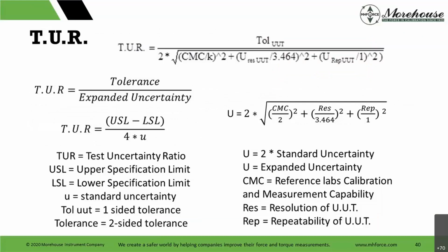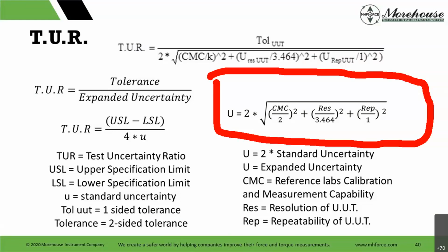The definition I like is ILAC P14 when it talks about short-term contributors. I'm putting this up as really a minimum, right? For this denominator, if we go to ANSI Z540, it's going to say you're going to include the reference standard uncertainty, the resolution of the device, and repeatability. Then it goes on to say stuff about transport, environmental conditions, and a lot of other things that may or may not be specifically related to your instrument. So though we're teaching this today, know that this definition is not the be-all and end-all. To me, it is very much the minimum required when we look at ILAC P14 and go with that guidance. Like I said, Z540.3 goes on and on about what goes in the denominator. So when I show these calculations today, we're using this definition.